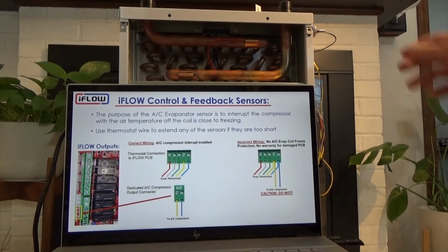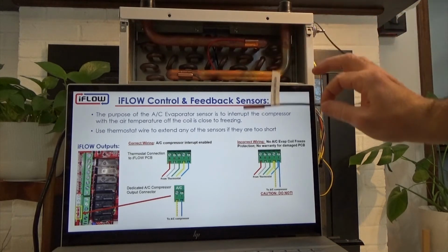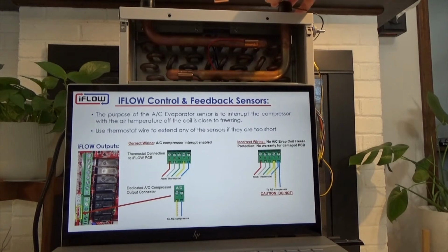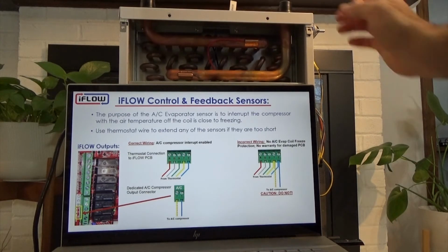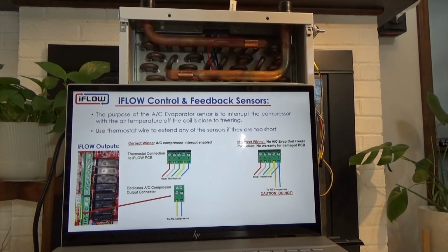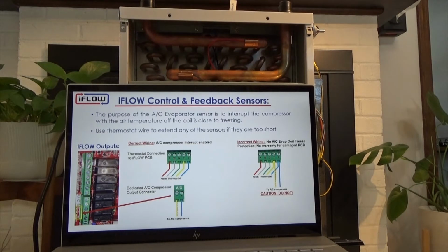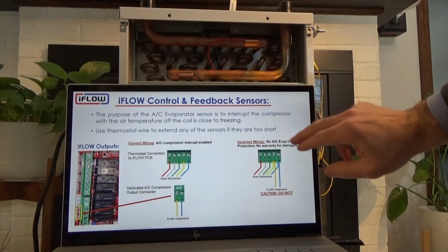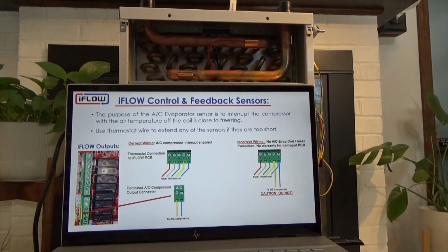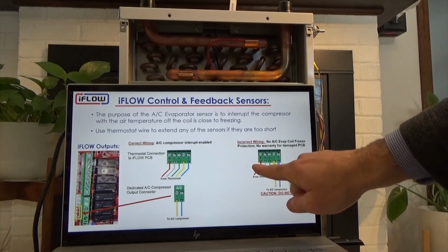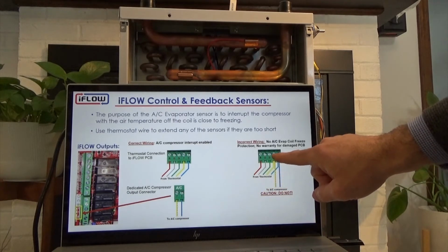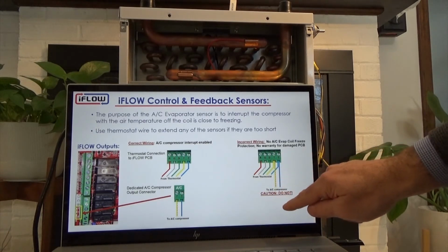So again, the purpose of this AC evaporator temperature sensor is to interrupt the compressor when the air temperature coming off the top of the coil is close to freezing. Again, 37 degrees Fahrenheit, 3 degrees Celsius or below. If we have wired the thermostat as you see here on the right, like so, as many contractors do because that's the way they've done it on the furnace, then we're going to get the call for cooling from the thermostat, and it's automatically going to send out the signal to the compressor.